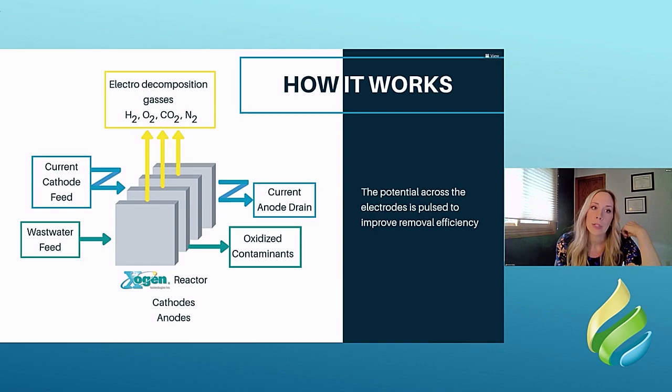And it matters in the sense of longevity, because if you have a sacrificial electrode, you're looking at weeks to maybe months where you can operate, but eventually you'll run out of material. And then you'd have to keep going in every 2 to 3 months and swap those out and put new ones in. These electrodes, though, have a little bit fancier material and different coatings on them. Because they're dimensionally stable, they're good for 10 to 20 years, depending on the particular application that you're looking at.